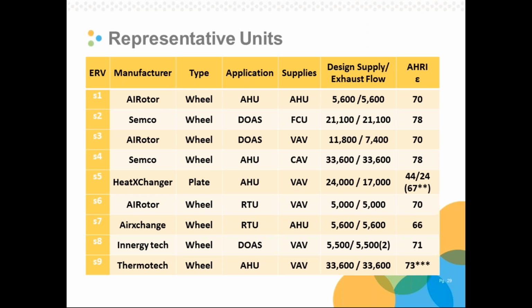These were in air handling units, dedicated outside air systems, RTUs. They served air handlers, fan coil units, VAV systems, in one case a constant volume system. They had design supply and exhaust flow rates ranging between about 5,000 and 34,000 CFM. All of them but one had an AHRI rated effectiveness, ranging between 66% and 78%. I will note that this is about 10 to 20% higher than the default in our TRM calculation. So on paper, these units are high performance with respect to some of our default assumptions. TRM is a technical reference manual, where we might go to estimate the savings from energy recovery units.